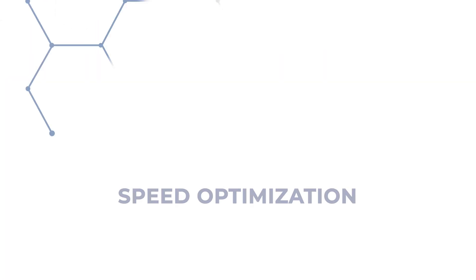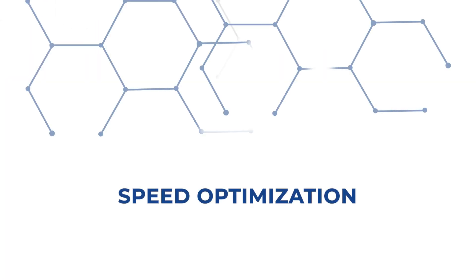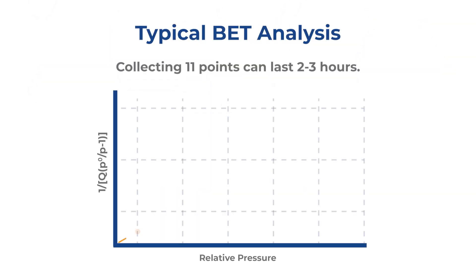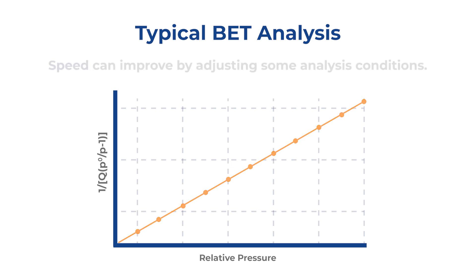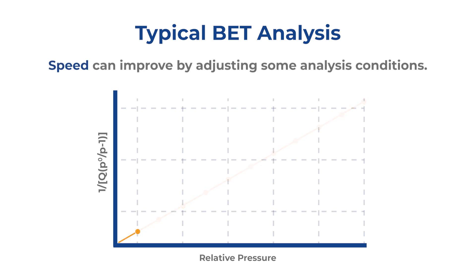Tip number seven: speed optimization. A typical BET analysis that collects 11 points can last about two to three hours. However, if throughput is more important than accuracy, the speed can be significantly improved by adjusting some analysis conditions.